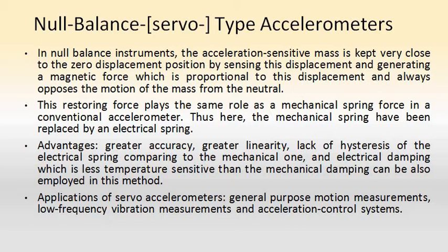The various advantages which we derive from this approach are greater linearity and lack of hysteresis of this electrical spring as compared with the mechanical one, and also in some cases electrical damping, which can be made less temperature sensitive than the mechanical damping, can also be employed here. And there is also the possibility of testing the performance of this device, both static and dynamic, before we do a test run, by introducing some external electrical forces into the system.